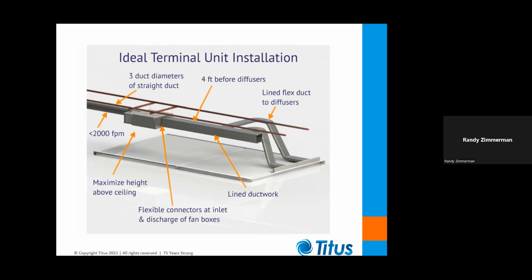Then it's a good idea to have at least 4 feet of lined duct before your first diffuser takeoff. Then it's a good idea to size that discharge duct for no more than 1,000 feet per minute. So I always think of terminal units as cutting velocity in half: 2,000 feet per minute on the inlet, no more than 1,000 feet per minute at the discharge, and then use a good quality lined flex duct to eliminate a lot of discharge sound from a terminal unit. Some people call lined flex duct flexible silencer.